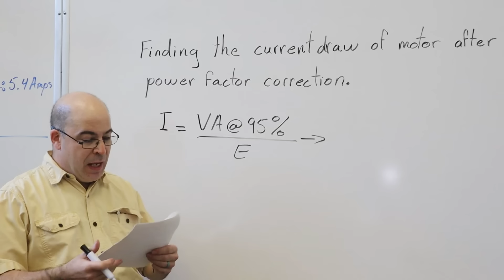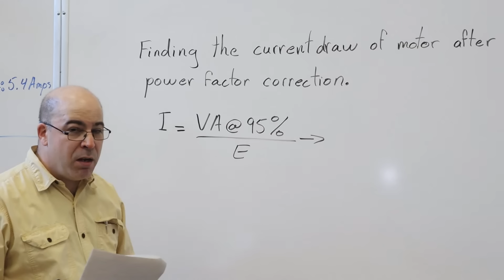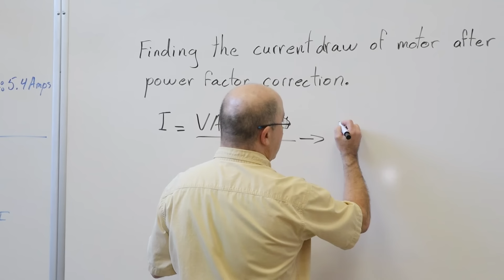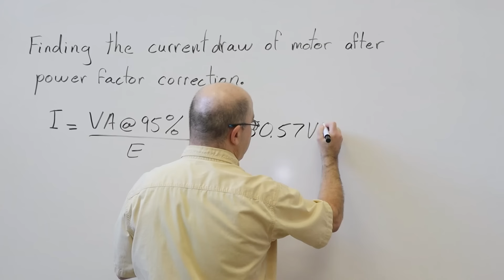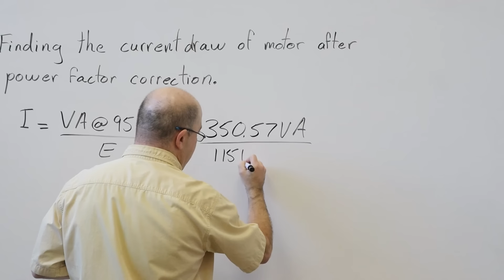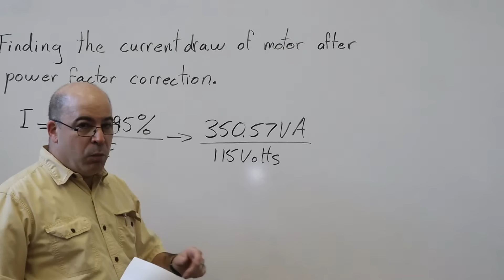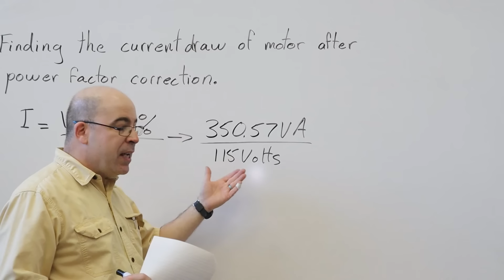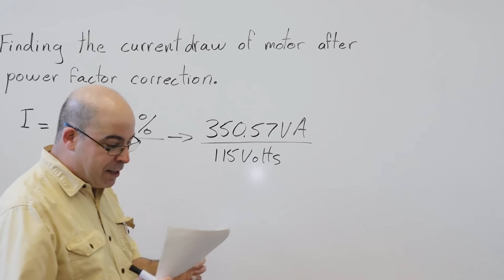So it's basically Ohm's law, but I'm taking the desired value of apparent power after power factor correction, and I'm going to divide it by the voltage that was listed on the nameplate of the motor, which was, in this case, 115 volts. So let's take that value of 350.57 VA, and we're going to divide it by the 115 volts. Now, this is going to give us a rough idea, because typically we have 120 volts, and when I've taken readings, depending on time of day, it could be as high as 122, 123. But this is going to give us a good general idea.